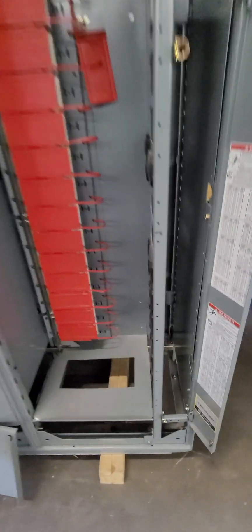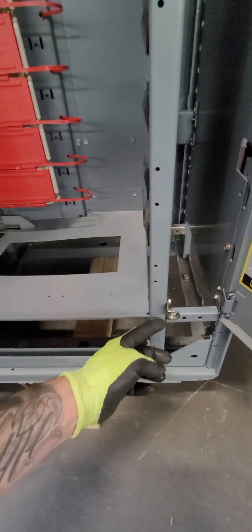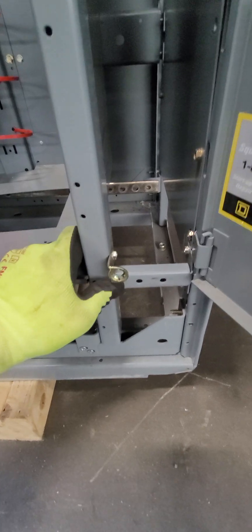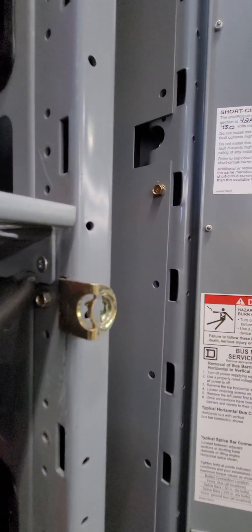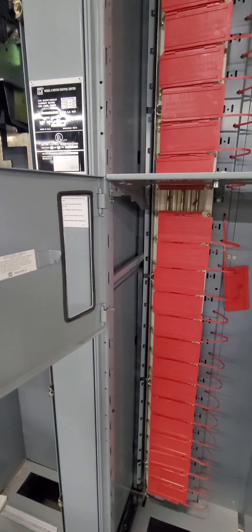The little item we forgot to mention was this little support bracket. There's actually no screw connection on one side — it's just pressure holding it — and there are two screws on the right side that fasten it in. It can flex a little bit; there's a little tang it locks into, but no actual screw on the left side. We've put that in, and now we've started to fit the cell. We put in a divider pan — it attaches here with screws, and also here, and some attach at other points. We're going to put one divider pan in, another across the bottom, attach our door, and put our bucket in.